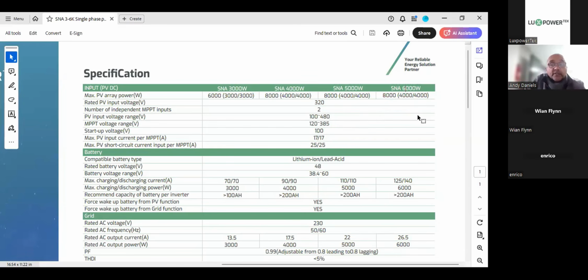The other thing that I also like to remind installers is that by going for the maximum of 4,000 watts per string, you're going to give you 8,000 watts input. But remember that our inverter is only a 6 kilowatt inverter, or 6,000 watt inverter. What happens to the other 2,000 watts? It will only be used, number one, when the battery requires charging or additional charging and you have load. So you've got to have loads of 6 kilowatts and a charge requirement, then it'll exceed the 6 kilowatts. Or alternatively, you might have low solar radiance days like today, when it's handy to have this size array on your roof, because you've got more exposure, and you might not get 8,000, but it gives you more exposure to get a higher yield for the day.